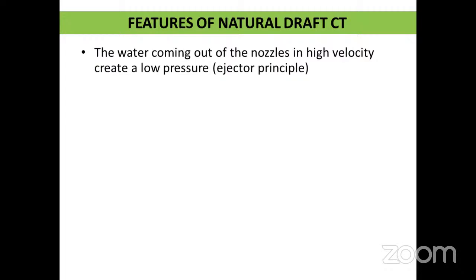We may presume like that. Actually, there are no fans, so there will be no electricity consumption. But the basic principle of airflow into the cooling tower is made by the water nozzles. The water nozzles actually spray the water with high velocity. Because of that high velocity, vacuum is created. This vacuum sucks the air from the surrounding of the cooling tower through the bottom opening, so that airflow is maintained. Because of making the water ejection at a high velocity, we need to increase the power of the circulating water pump. Otherwise, the circulating water pump will be of a lesser capacity only. But this is very marginal compared to the fan capacity. This is only marginal, but there will be an increase in energy consumption.